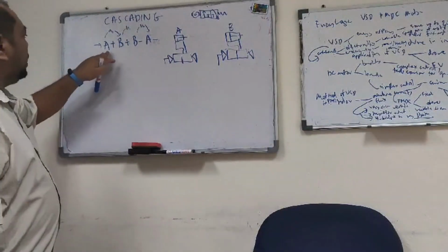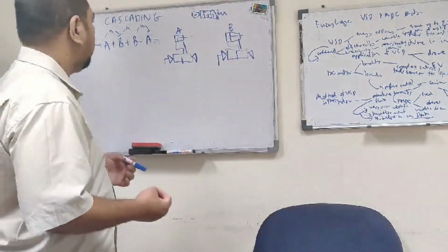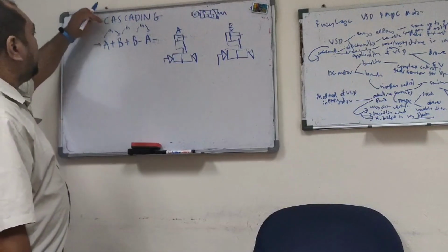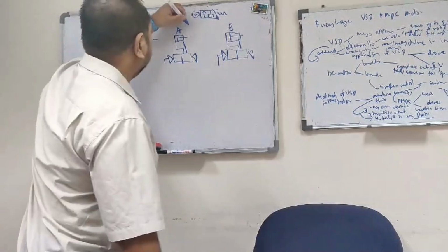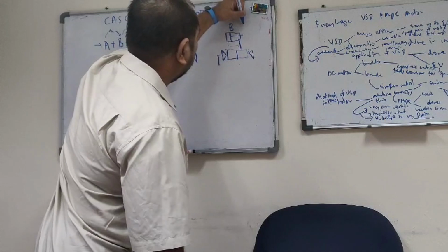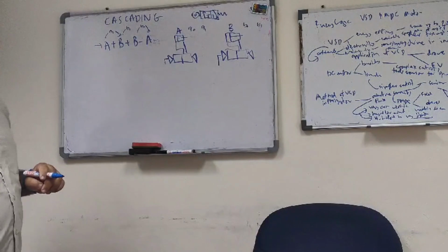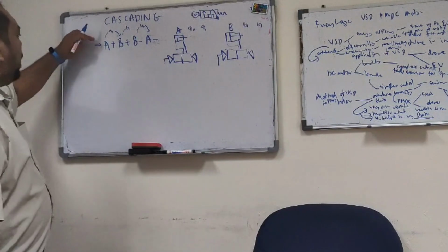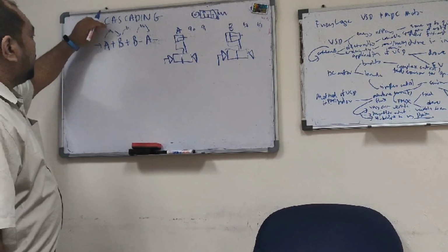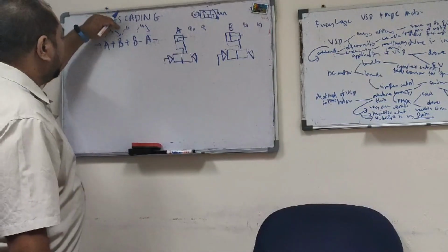For example, with the sequence A plus, B plus, B minus, A minus, you have to note the consequence of each cylinder action. A0 is for the retract and A1 for the extend of cylinder A, B0 for the retract and B1 for the extend of cylinder B. A plus will hit sensor A1, and due to A1 being activated, we want extension of cylinder B, so B plus.